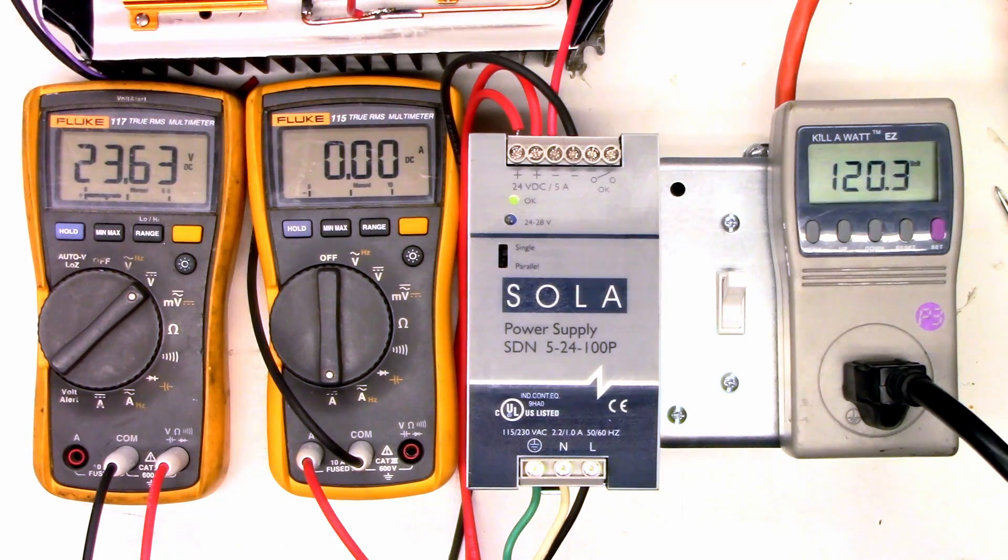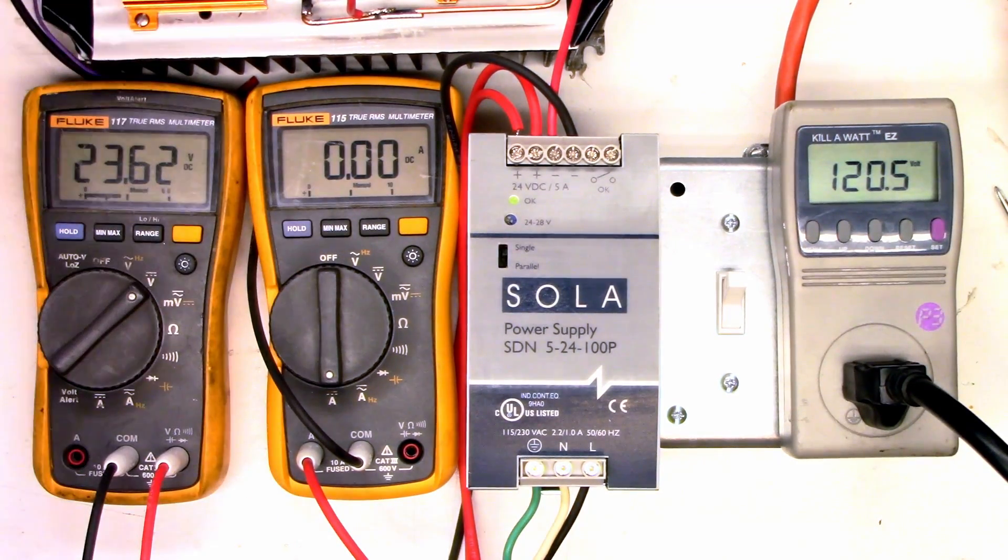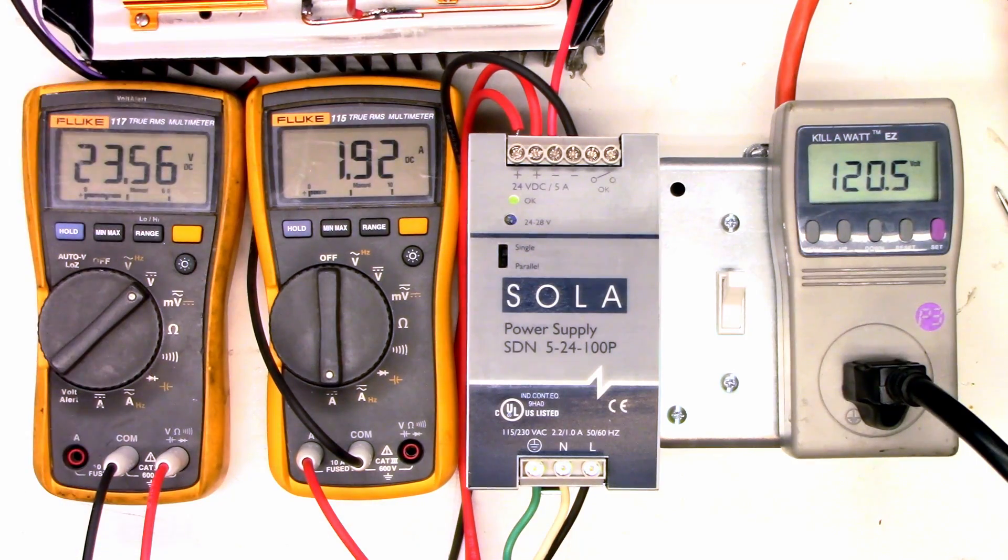I'm going to go ahead and switch this on. It's going to turn on the Sola and the Kill A Watt, and we see we have 23.6 volts output right now, and we have 120.5 volts going into it, and 0 amps on the amp meter. Let's go ahead and turn on the first load, 1.93 amps, 23.5 volts coming out of it.